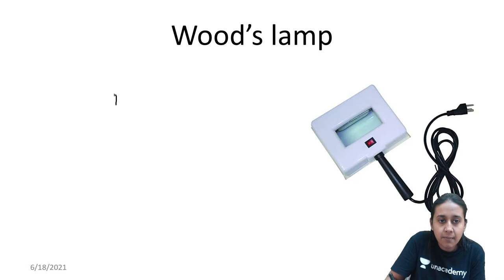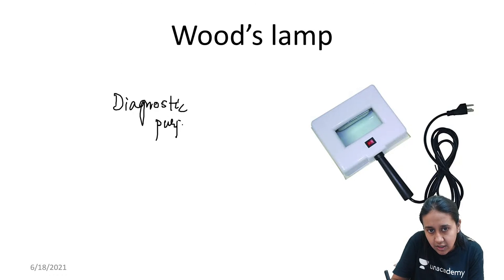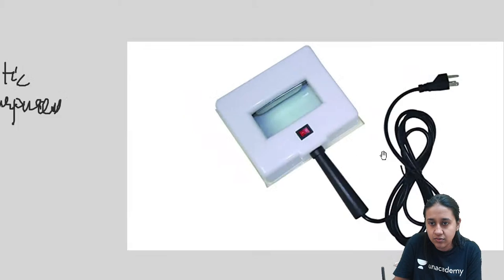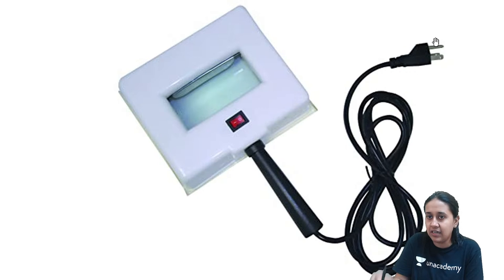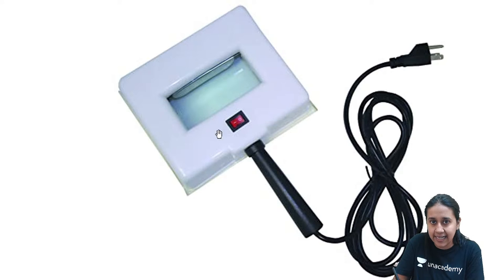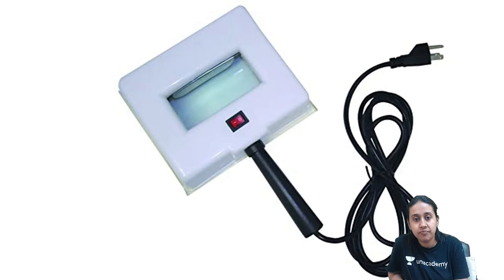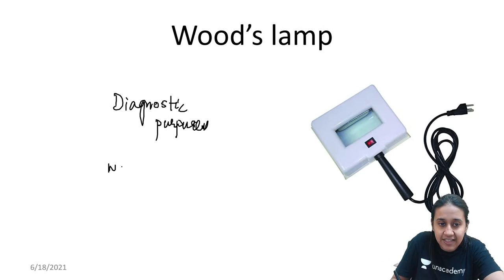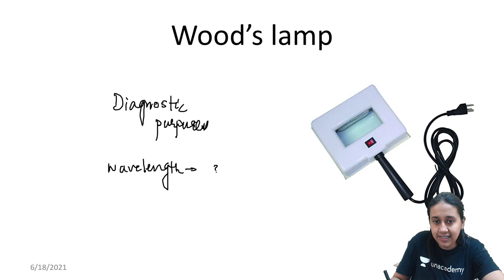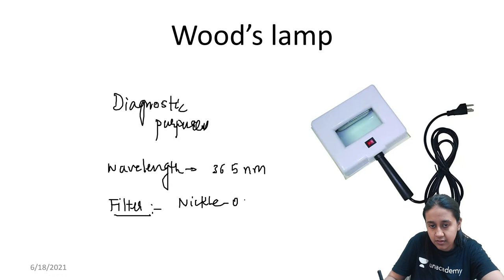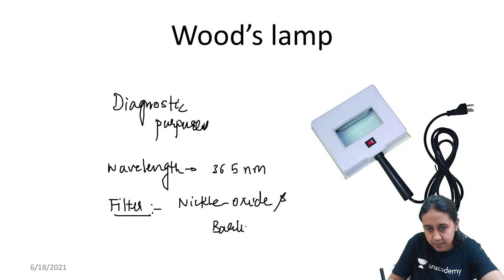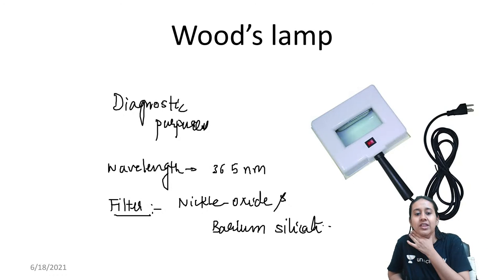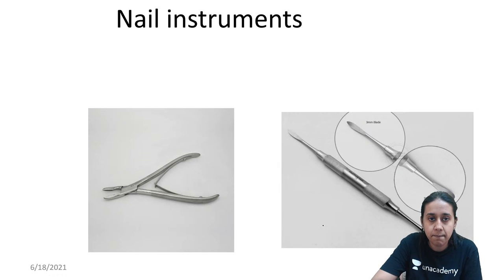The next instrument is the Wood's lamp, a bedside diagnostic instrument. It has a glass window over a rectangular box, with a bulb below that emits UV radiation. A filter made of nickel oxide and barium silicate allows only radiation of 365 nanometers to come out. So the wavelength emitted by the Wood's lamp is 365 nanometers, filtered through nickel oxide and barium silicate.